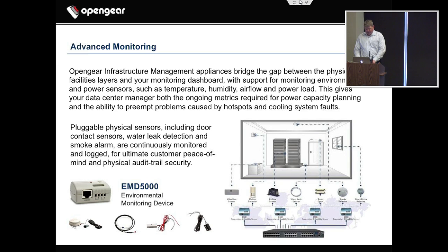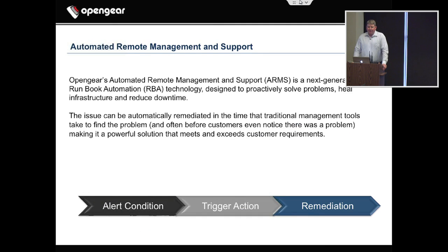Does this thing work any differently than the built-in monitor, the contacts and whatnot on the ACM? Not really, no. Yeah, almost identical, except the built-in ones don't have humidity. Yep. They only have temperature. So it has a little bit more of an advantage.